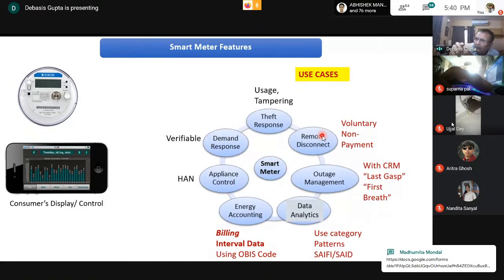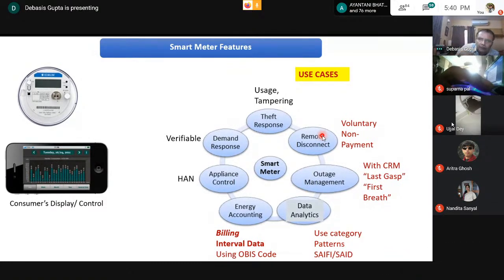Even though it's hardly 1 square inch in size, it's capable of switching 200 amperes. The Indian standards ask for relays on both phase and neutral, because we are very careful. The European and US standards ask for only one relay, on the phase.